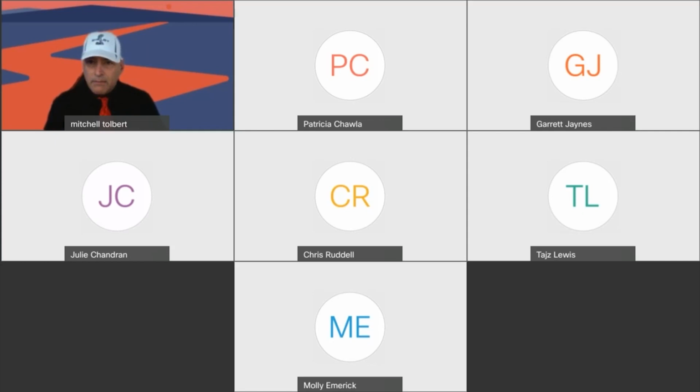Let's see. Water heater amendments still favor gas-fired over electric. So there was a recent change in the state legislature that basically prevented anyone from requiring a specific type of utility or energy source be used, which effectively means that the gas versus electric was really now a design or an owner option and not one that we could regulate. However, if the gas-fired is not used and it's electric, then the timers are definitely required, and that's part of the local amendments.